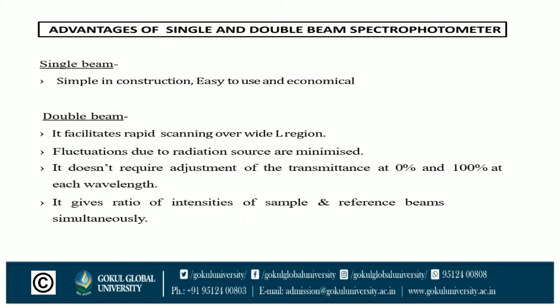The double beam facilitates rapid scanning over a wide wavelength region. Fluctuations due to the radiation source are minimized. It does not require adjustment of the transmittance at 0% and 100% at each wavelength, and it gives the ratio of intensities of the sample and reference beams simultaneously.